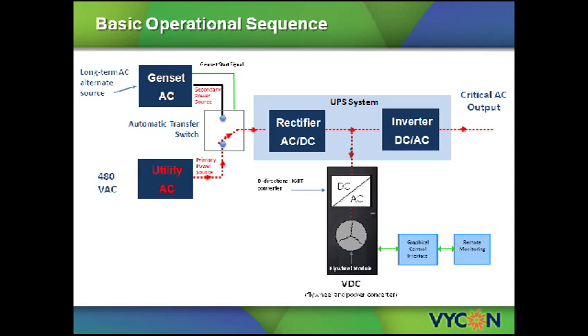The purpose of the ATS is to: 1. Detect a loss of power from the utility source in order to provide a start signal to the standby diesel generator, and 2. Provide a mechanical switchover from the primary power source to the secondary power source.